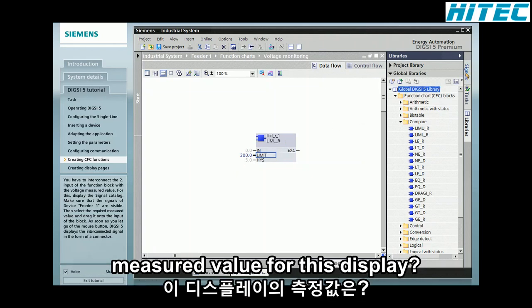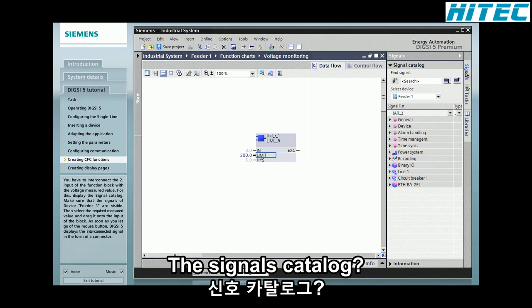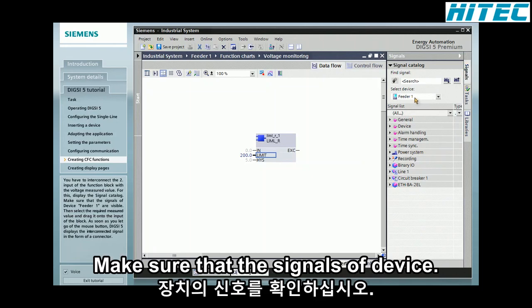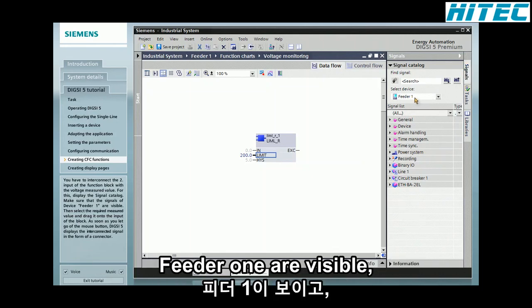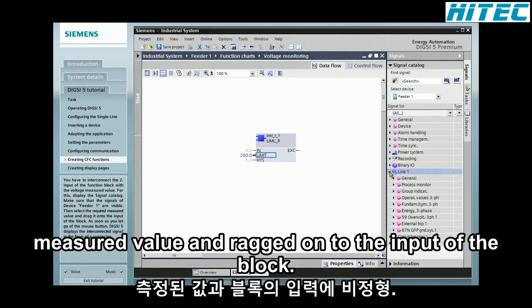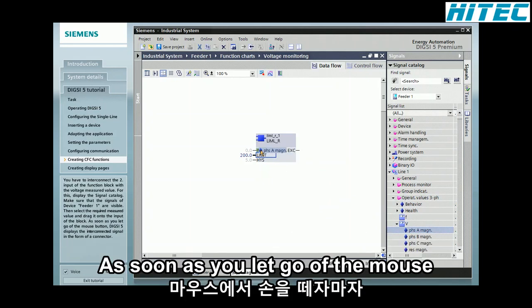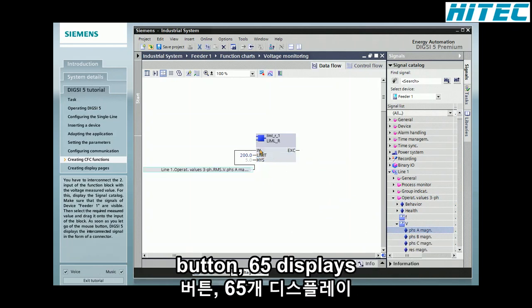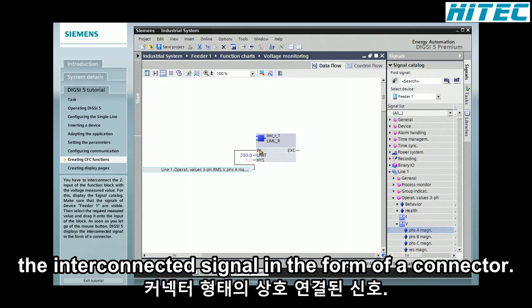For this, display the signal catalog. Make sure that the signals of device feeder 1 are visible. Then select the required measured value and drag it onto the input of the block. As soon as you let go of the mouse button, DIGSI 5 displays the interconnected signal in the form of a connector.